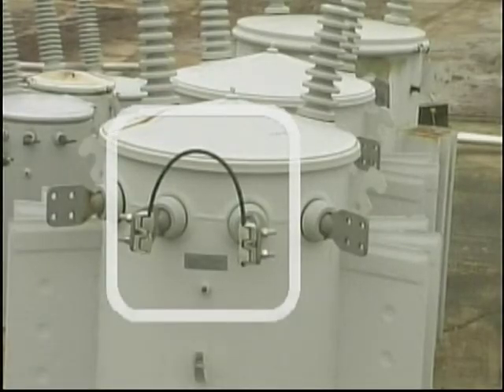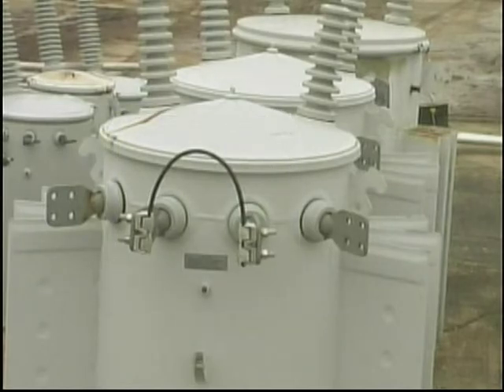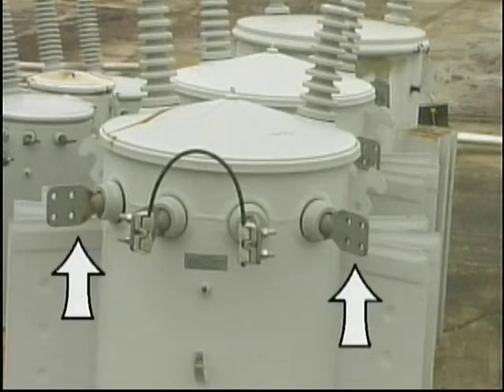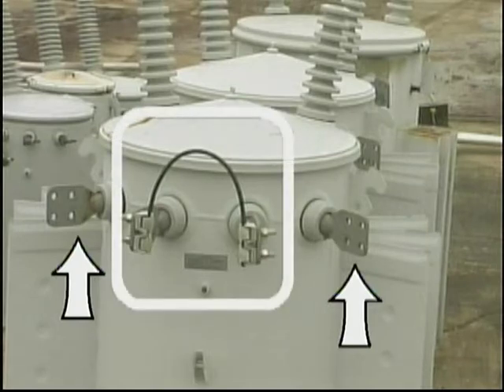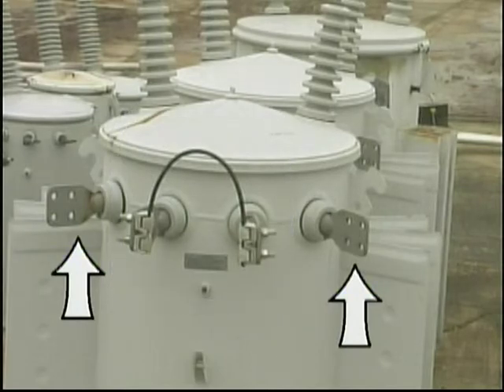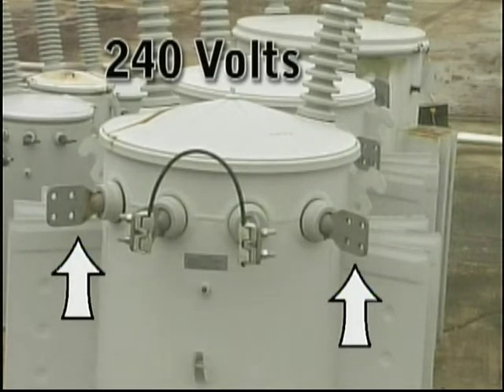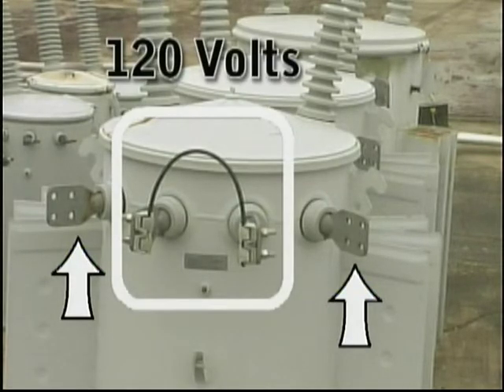Here's what it looks like in the field. With this jumper in place, the connection between the X2 and X3 bushings functions as a single bushing. The X1 and X4 bushings become the hot legs of the unit. The combination X2 and X3 bushing serves as the ground point between the two secondary coils. Connections to the X1 and X4 bushings will provide 240 volts. Connections between either the X1 or the X4 bushing and ground will provide 120 volts.